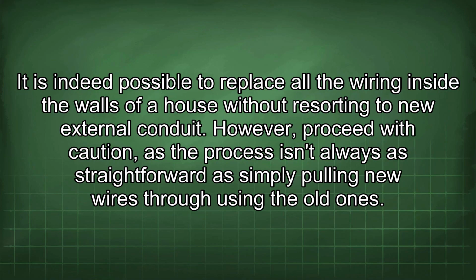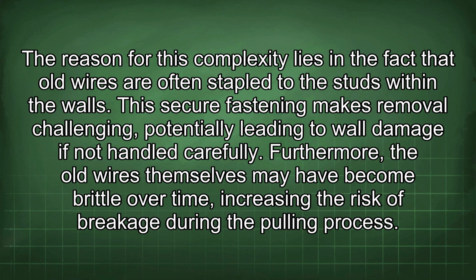It is indeed possible to replace all the wiring inside the walls of a house without resorting to new external conduit. However, proceed with caution, as the process isn't always as straightforward as simply pulling new wires through using the old ones. The reason for this complexity lies in the fact that old wires are often stapled to the studs within the walls. This secure fastening makes removal challenging, potentially leading to wall damage if not handled carefully.